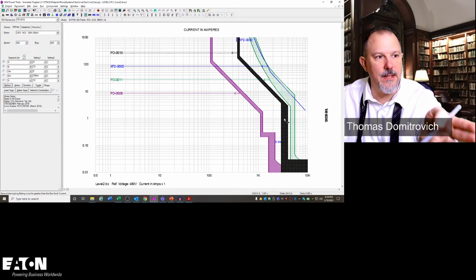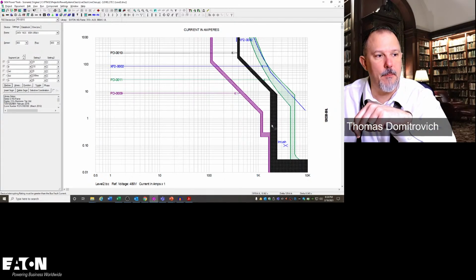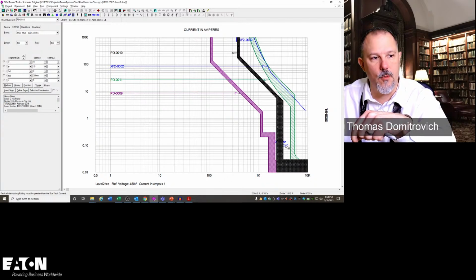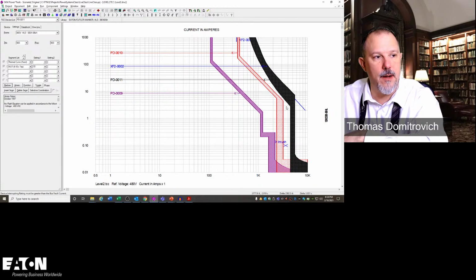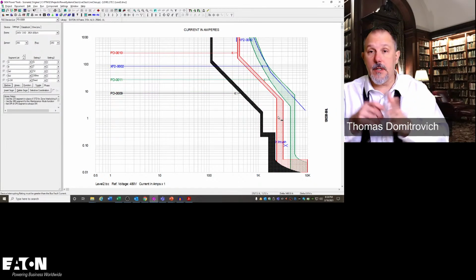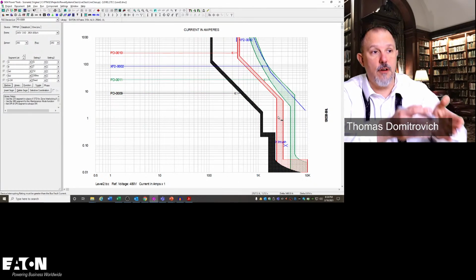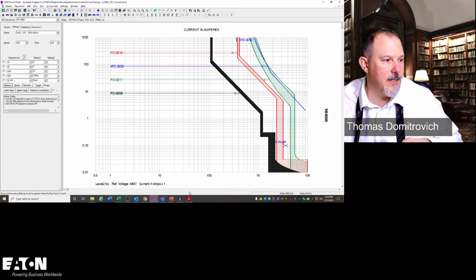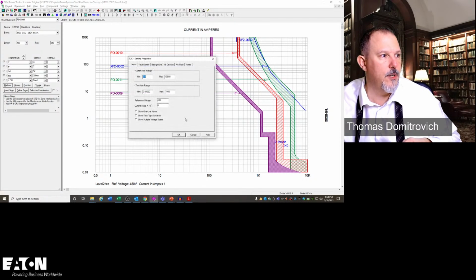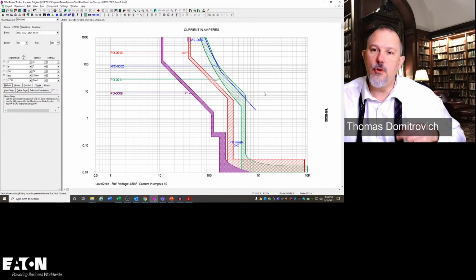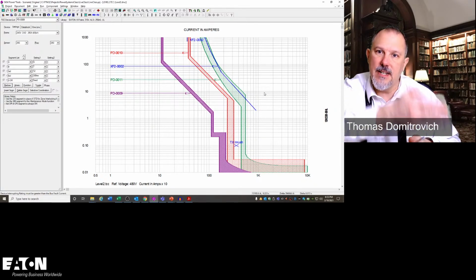So I know based on the tables that these two breakers work for the fault current at the secondary, but my problem was I was overlapping in the short time delay. So I'm going to move that up. I don't have to worry about that inrush because the inrush is based on the primary of the transformer. This is my primary, so there are my three breakers. This is what I would typically do. I would show the transformer damage curve, and instead of current times 1, I would change this to current times 10. And you could plot the thermal damage curve for the conductors on here as well.